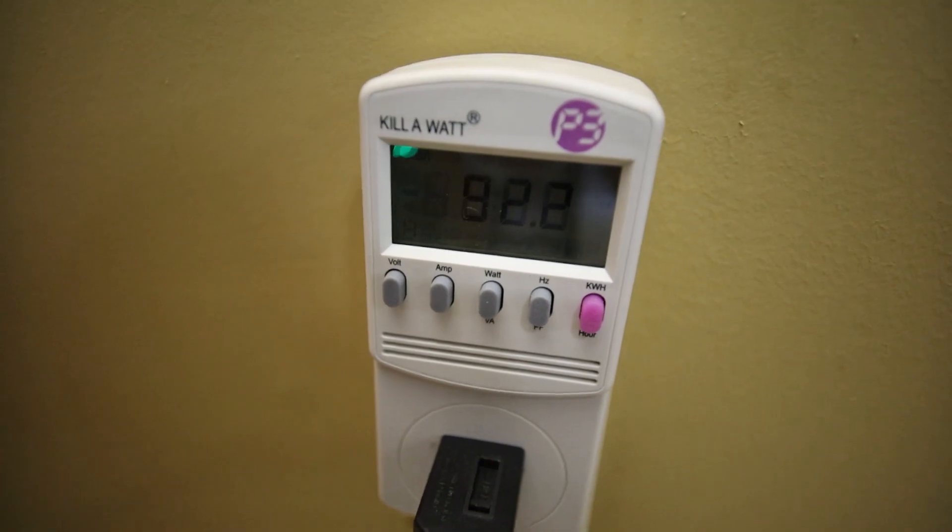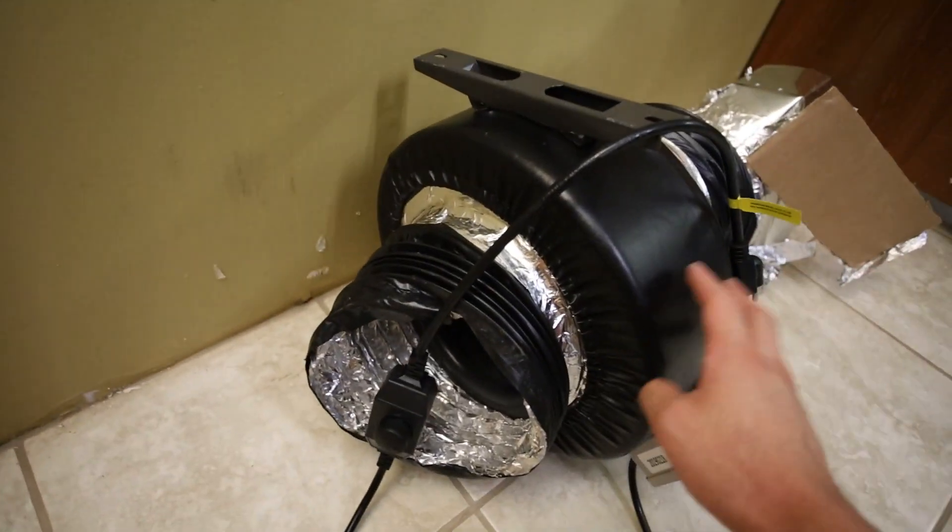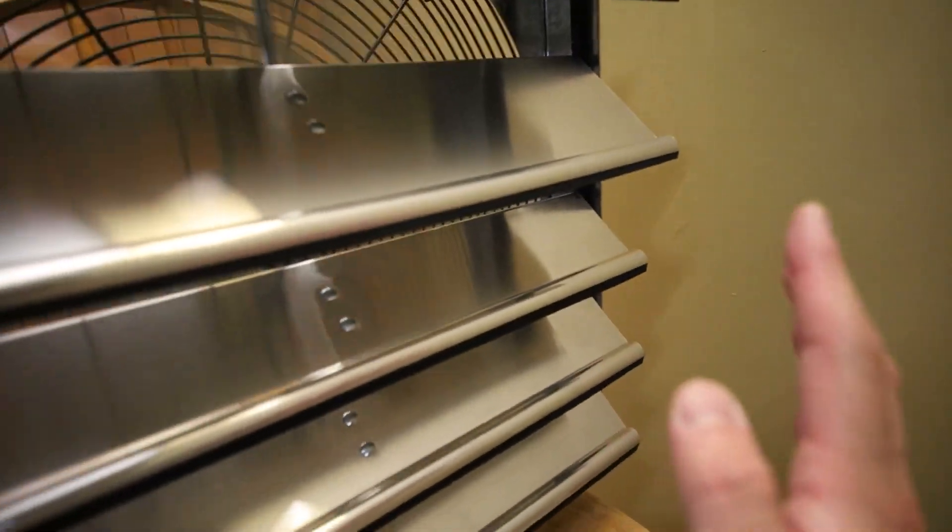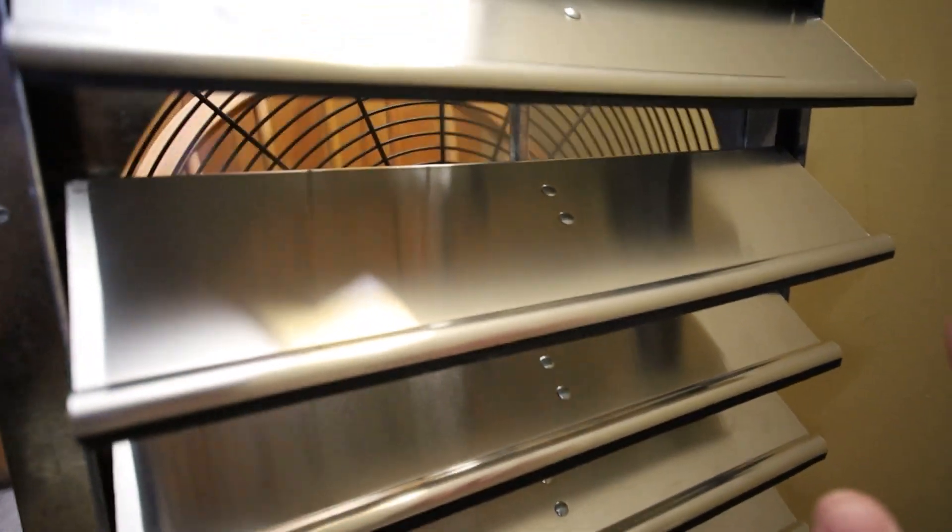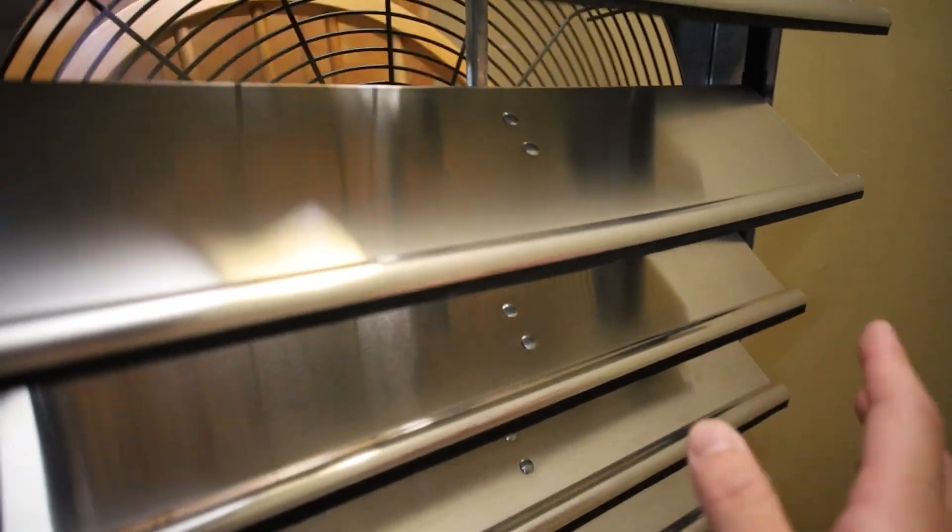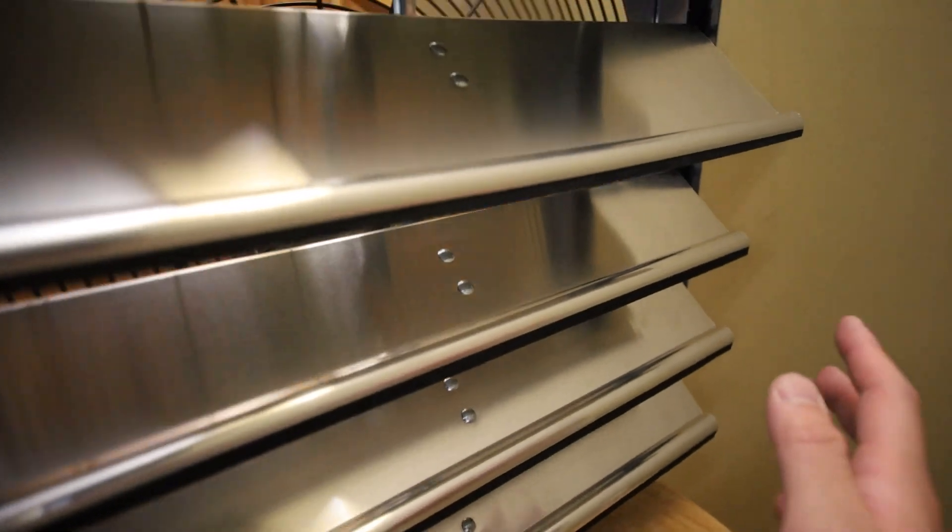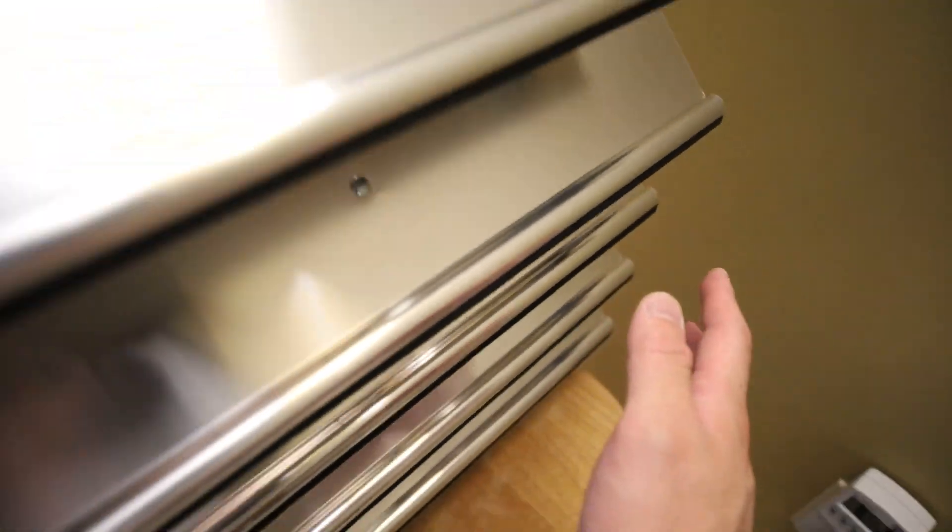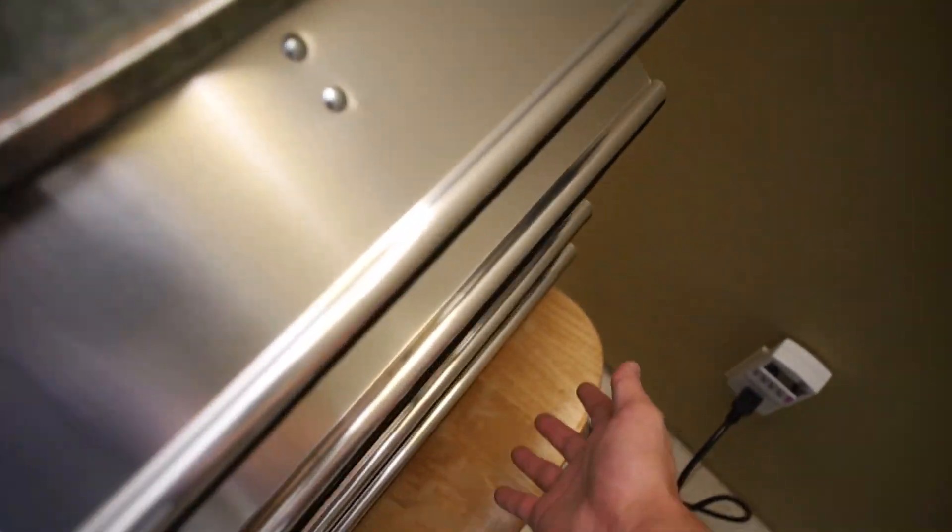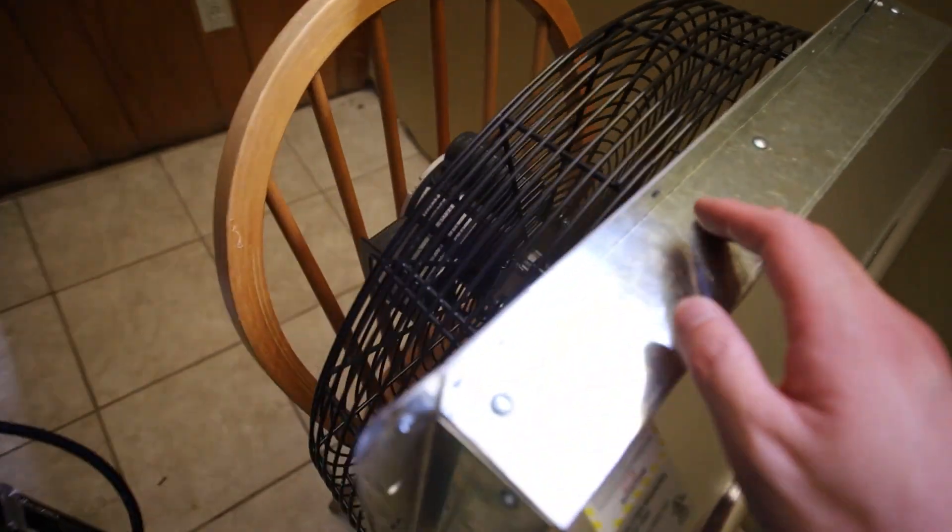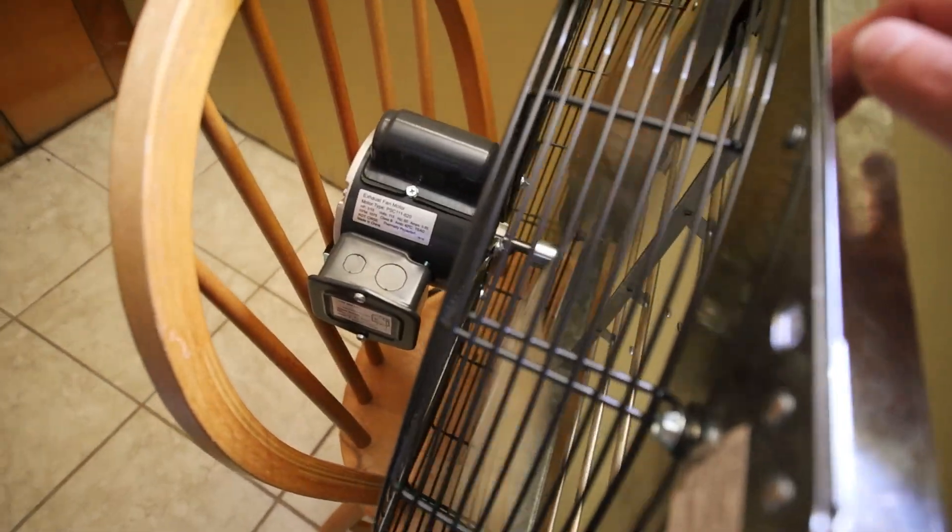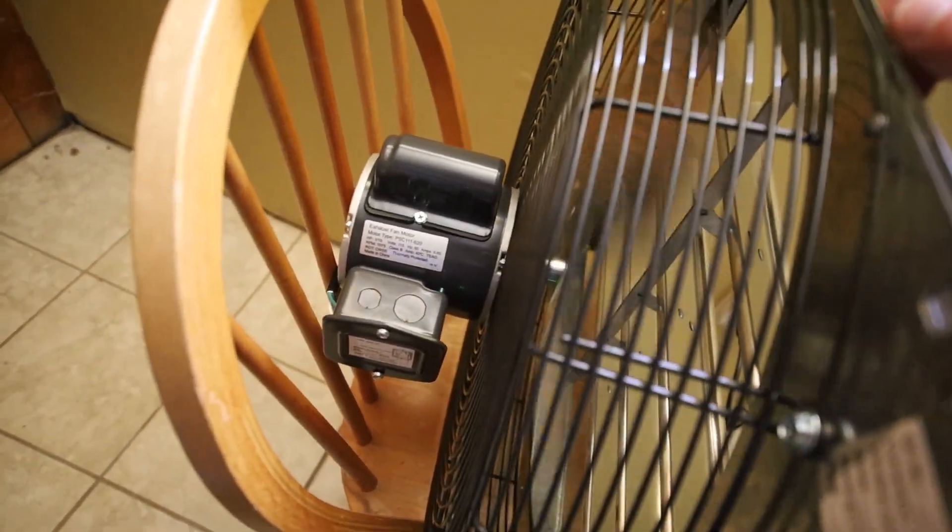I think that's actually much less than my eight inch inline fan. So yeah, actually there's a lot of air coming out of this fan right now. Supposedly 1700 to 1800 CFM is supposed to be coming out of this 18 inch exhaust fan. That seems about right and it's not loud at all. It's actually really quiet.